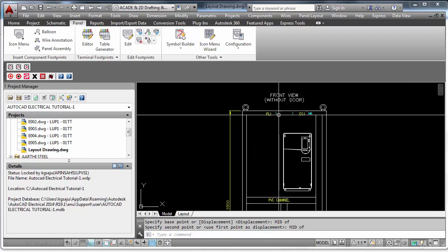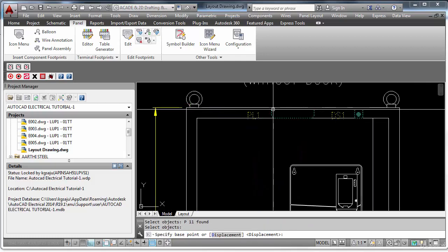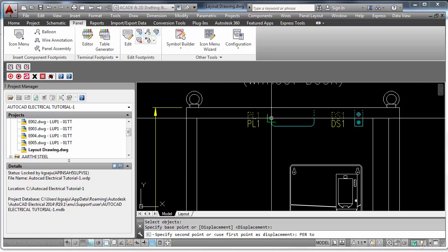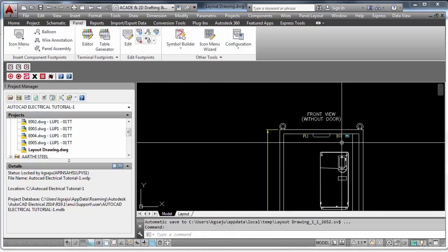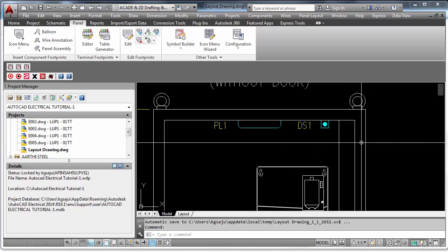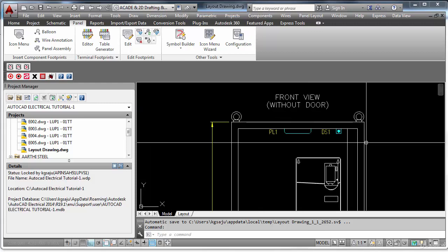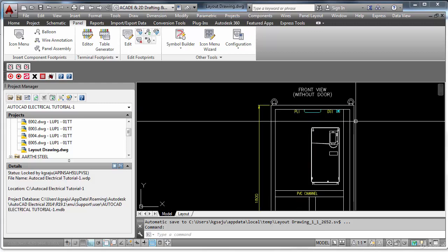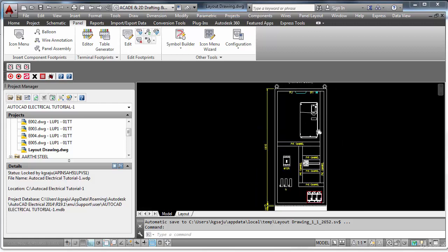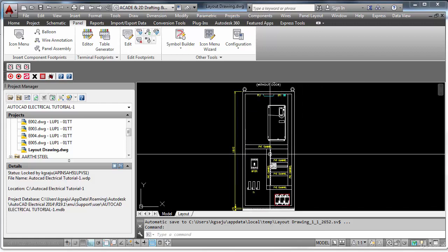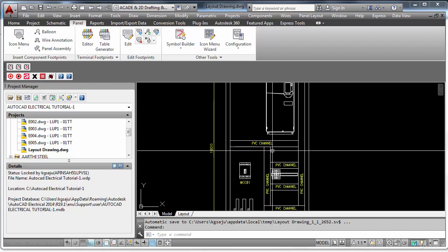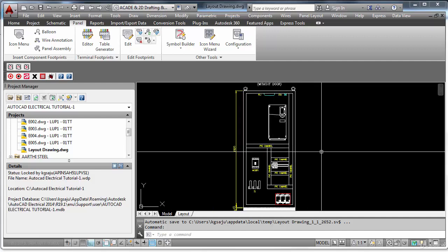And if you want, I can put this thing, panel lights, illumination lights. I'm going to put it here with a door switch. This is a door switch, door limit switch. When the door opens, the light glows and the fan stops. Normally it comes with one NO, one NC contact. NO contact we will put in the light and NC into the fan. When the doors open, the fan will not work.